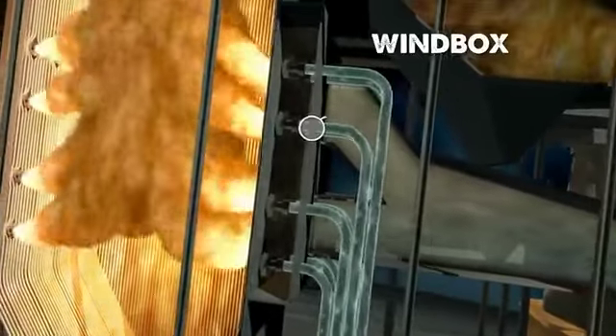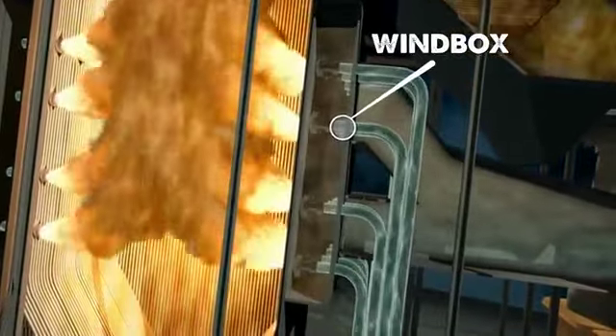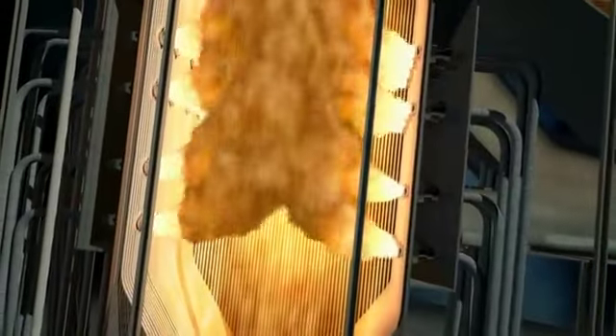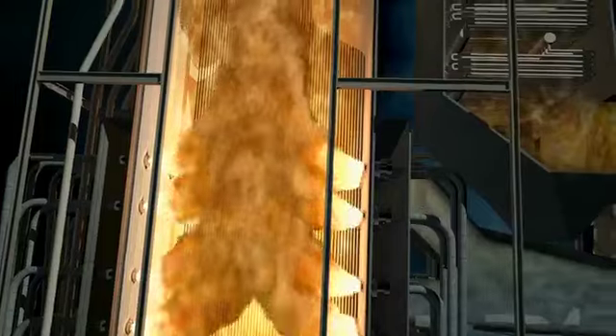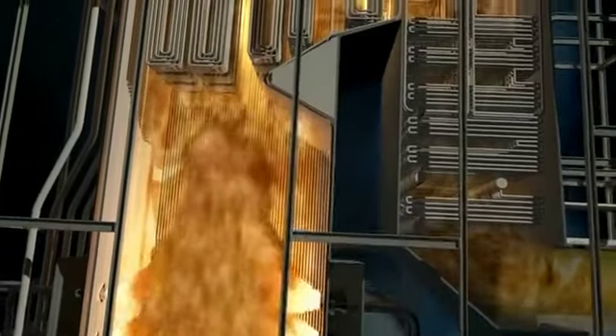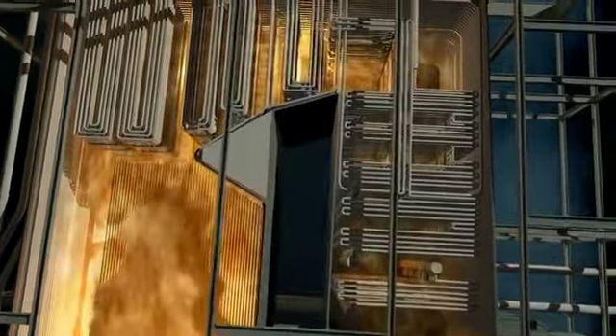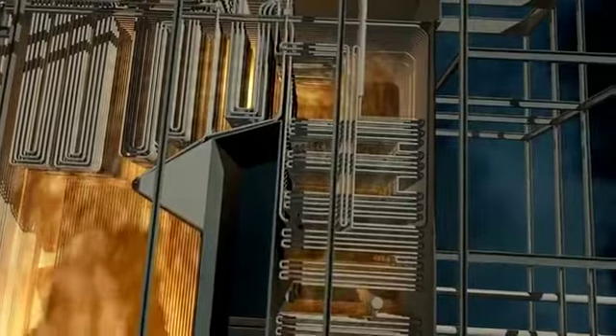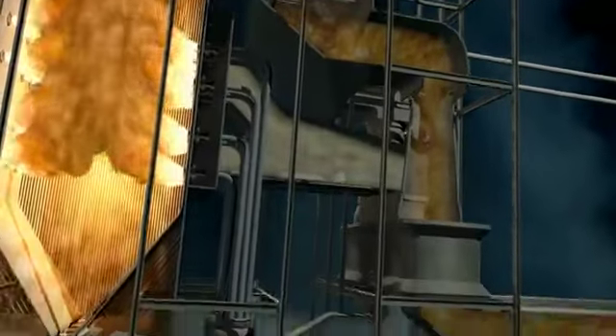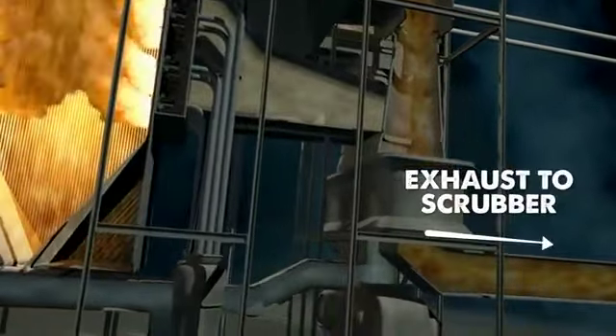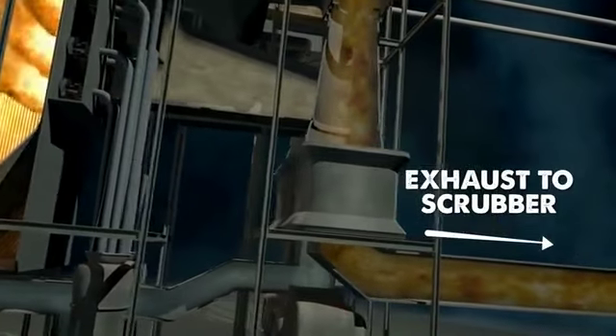The hot forced air and coal dust converge in the wind box, where the mixture is blown out through burners and ignited inside the firebox, transferring radiant heat to the water-filled tubes. The hot gases flow upward, heating the rest of the system through convection, before passing through the air preheater and ultimately flowing into the scrubber, where pollutants are removed.